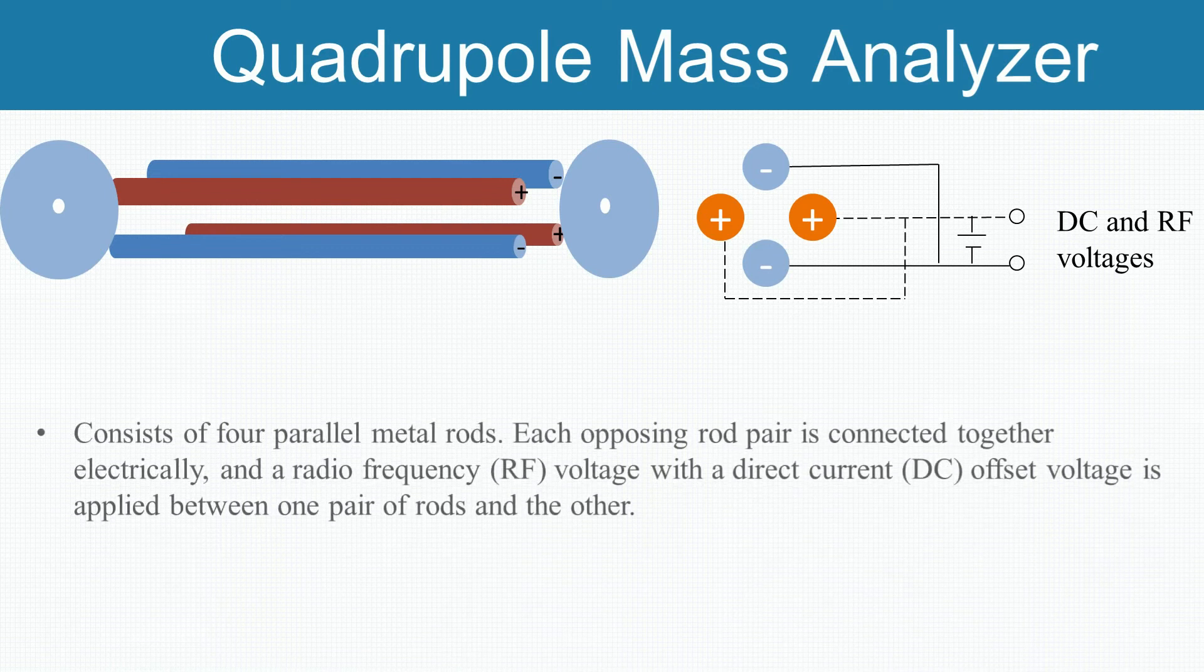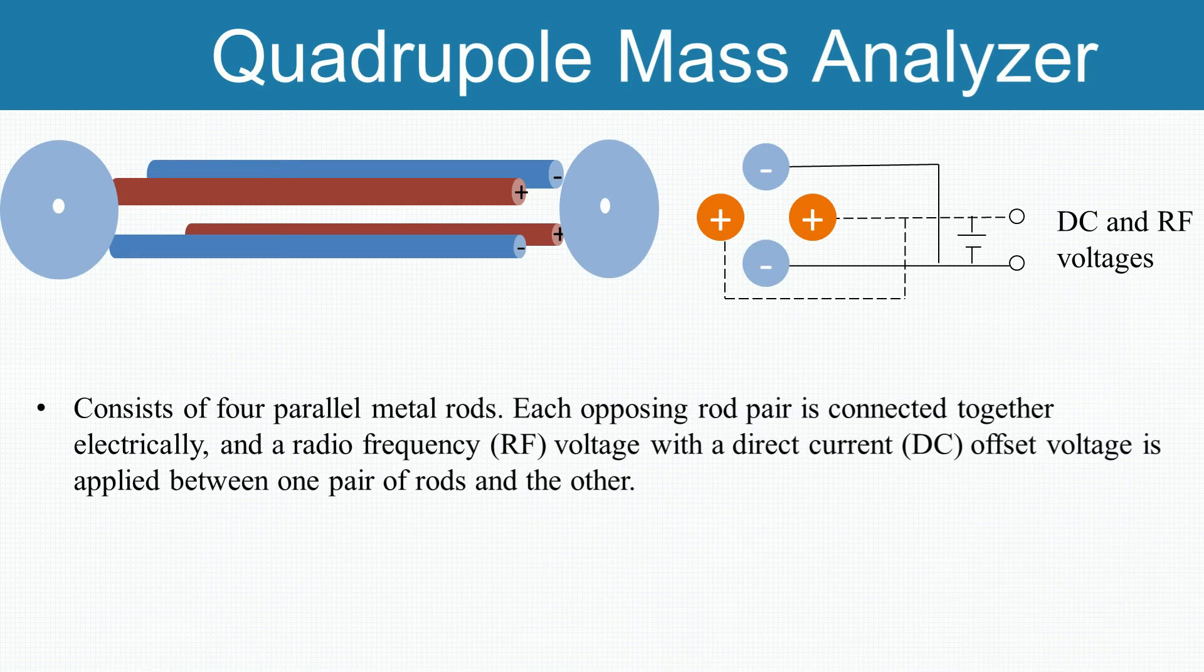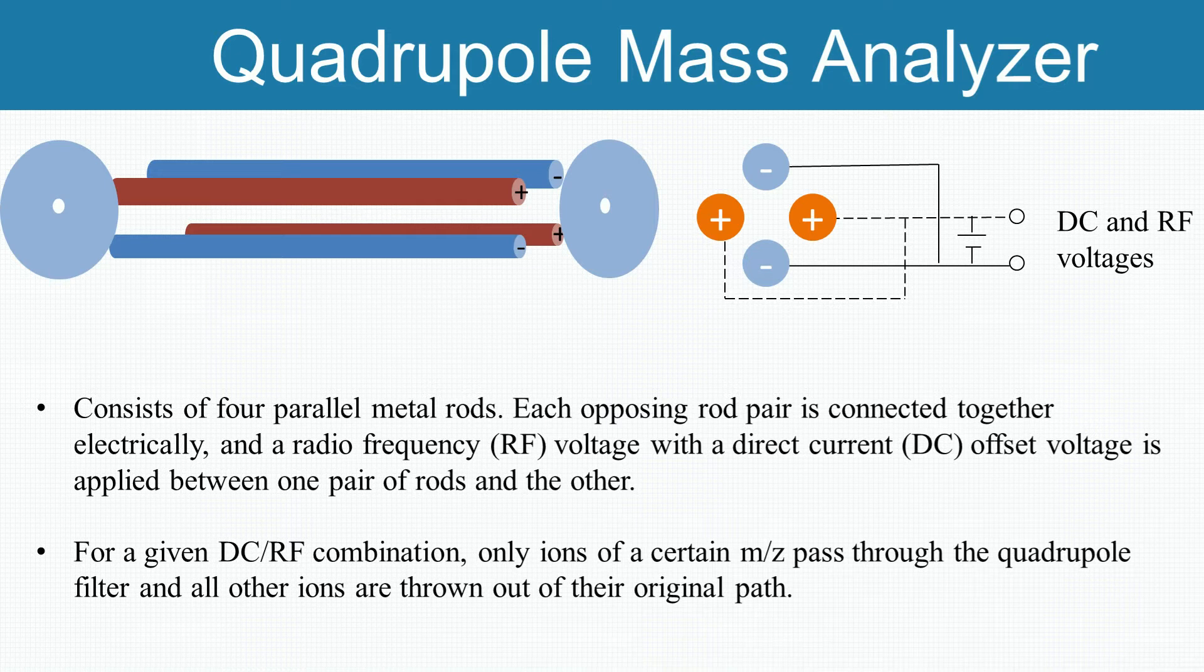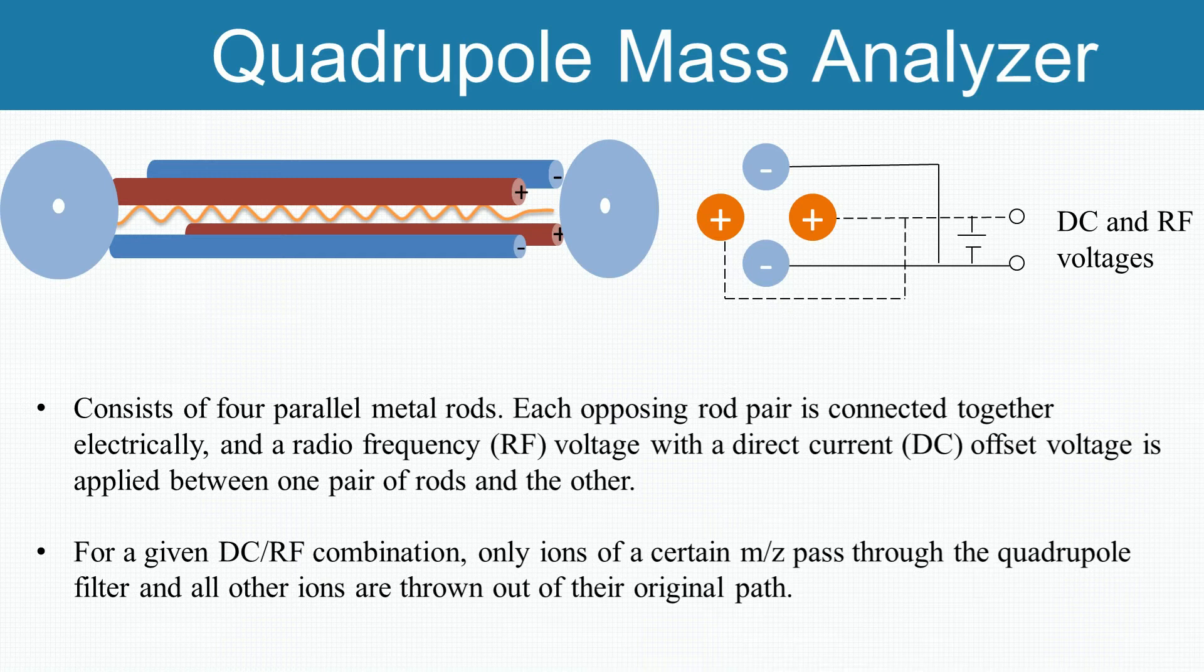Quadrupole consists of four parallel metal rods, and each opposing rod pair is connected together electrically. One pair of rods is applied with a radio frequency voltage, while another one is applied with a direct current voltage. At a given frequency voltage and direct current voltage combination, only the ions of a particular mass-to-charge show a stable trajectory and can be transmitted to the detector, while other ions with unstable trajectories don't pass the rod, because the amplitude of their oscillation becomes infinite. By changing frequency and direct current voltage in time, usually at a fixed ratio, ions with different mass-to-charge values can be transmitted to the detector one after another.